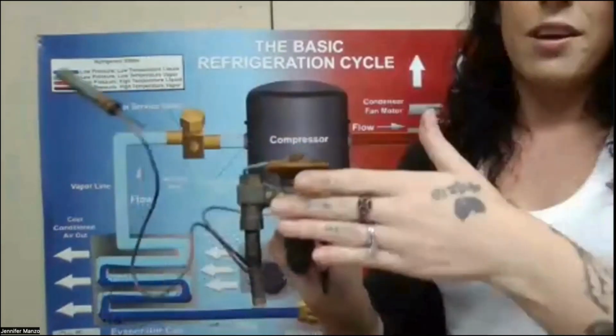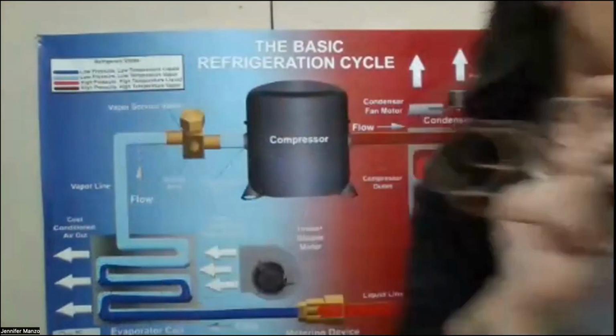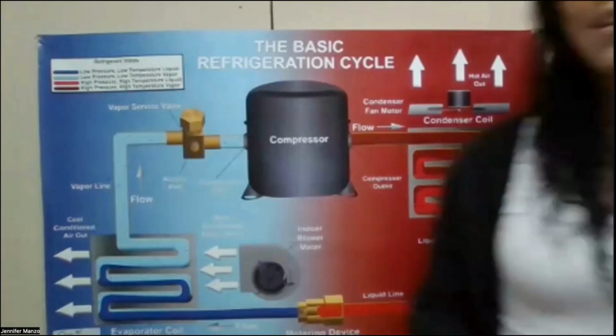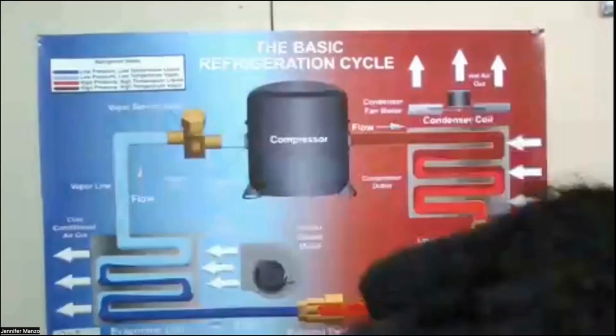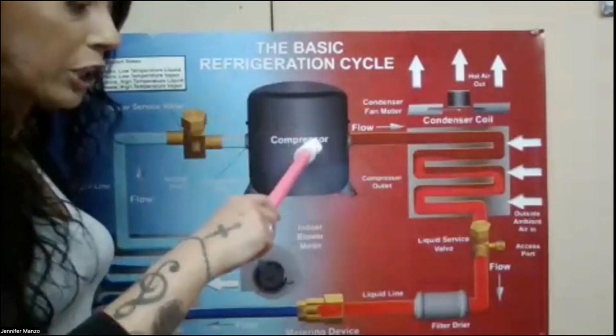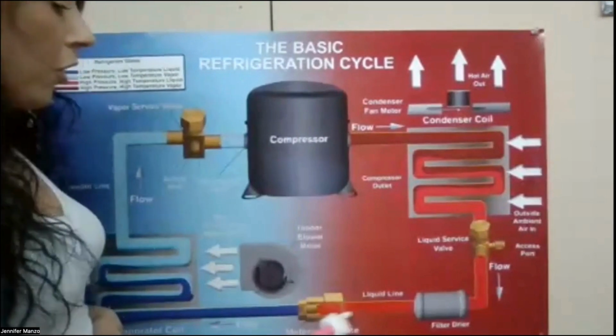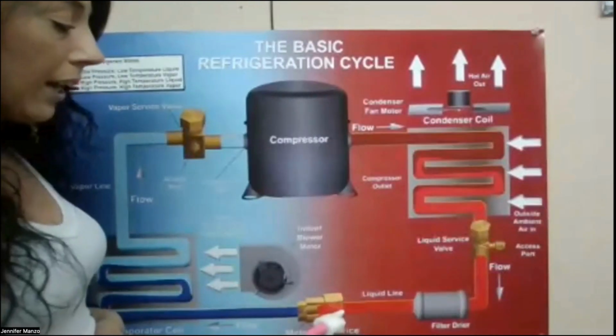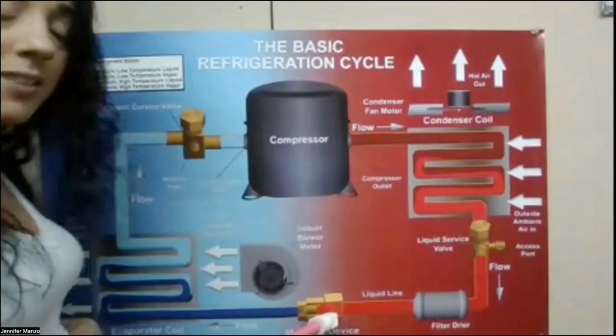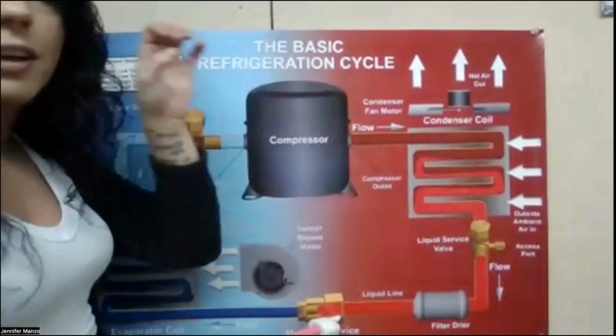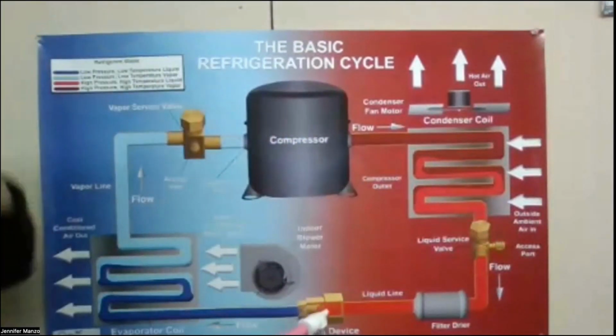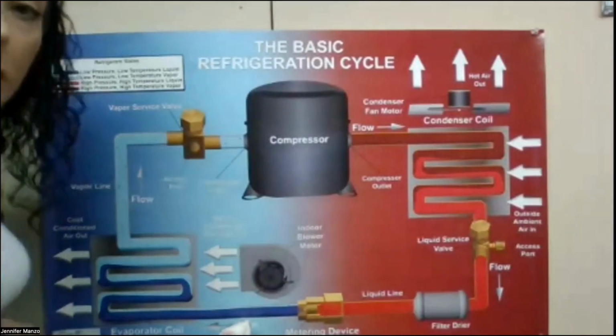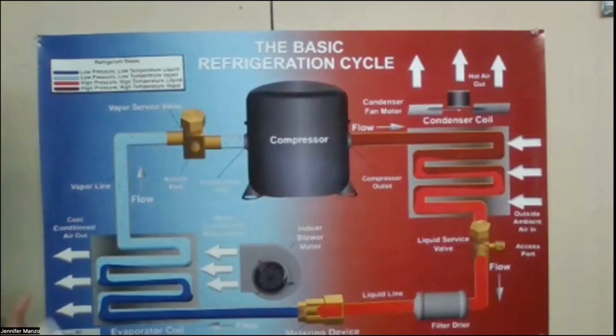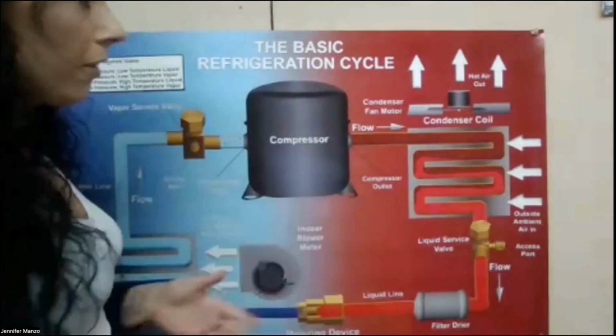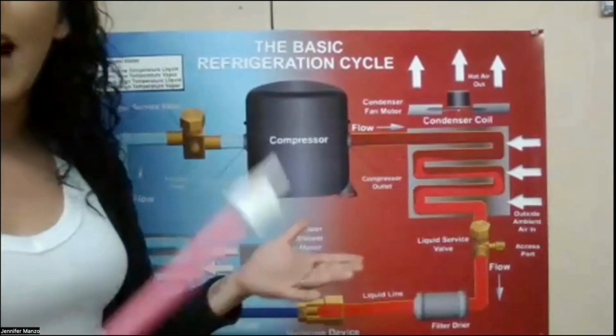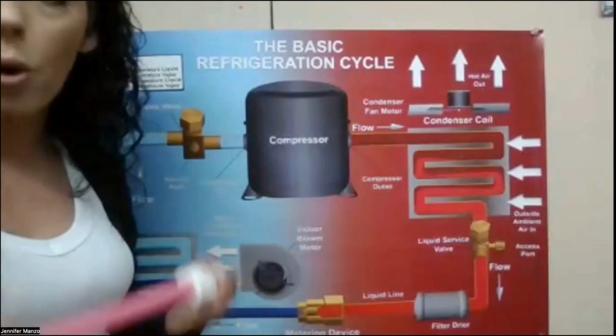So here's your metering device. This metering device's job is to lower the pressure. So that component is the exact opposite of this component that we just were talking about, this compressor. This compressor's job is to raise the pressure, metering device's job is to lower the pressure. So what it's going to be is a hot liquid coming here, a hot high pressure liquid coming through here. When it gets to the metering device, it's going to meter it. It's going to squirt out just as much refrigerant as the rest of the system needs. And then it's going to come back out as a saturated liquid that's low temperature, low pressure on the other side. So when we talk about a high side and a low side, right? Anything that is hot, anything that is high pressure is your high side. Anything that is low pressure, that is cold, is your low side.